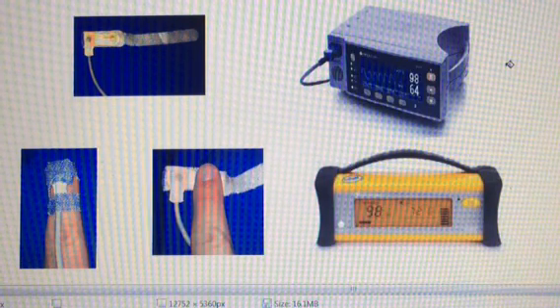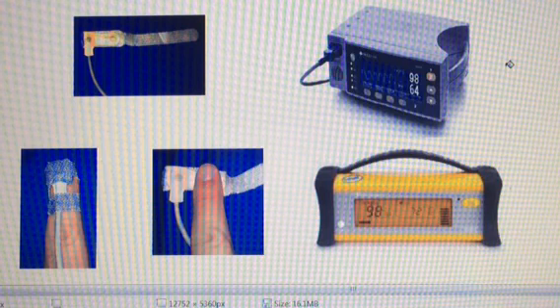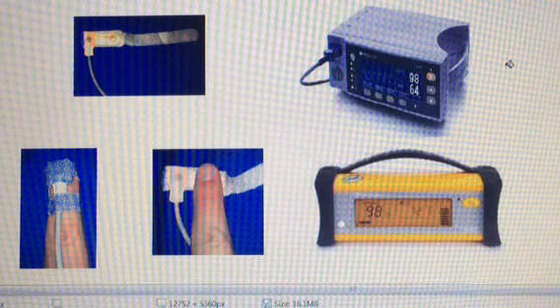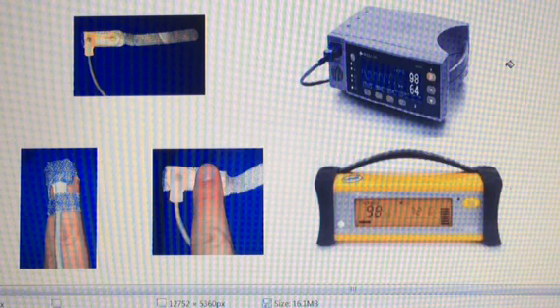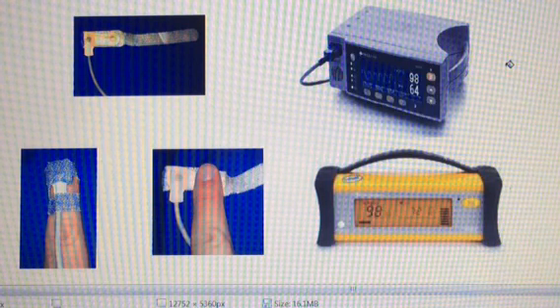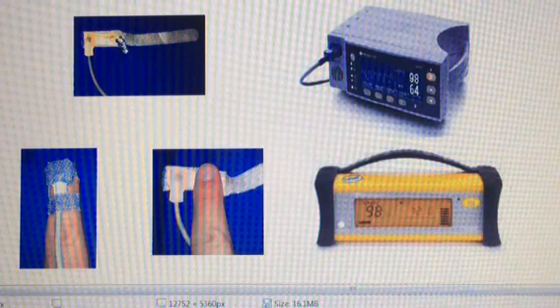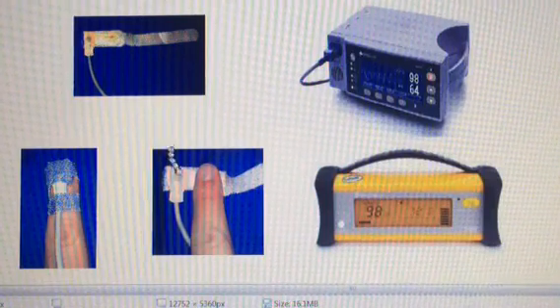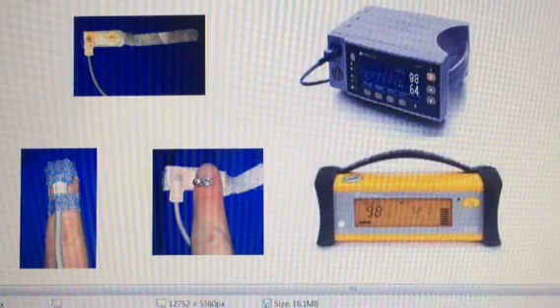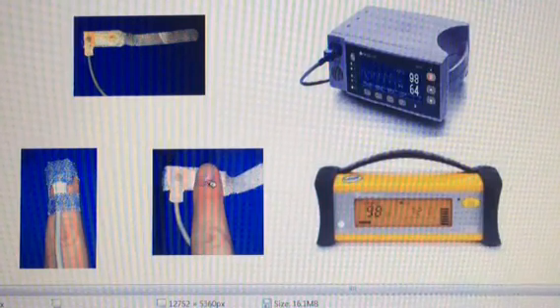If there are no signs or symptoms of distress, there are several things to check. Check the probe. Is it plugged in? Is it in place? Is the sender and the receiver on opposite sides of the finger, and are they facing each other?